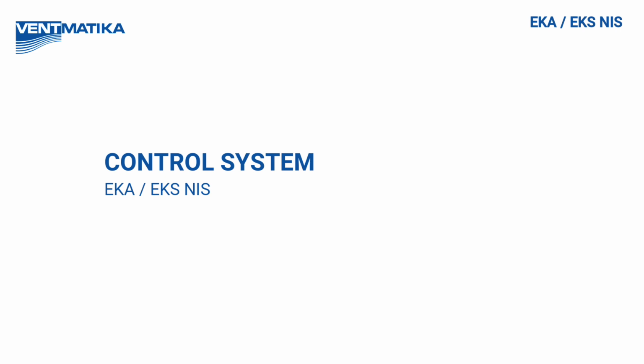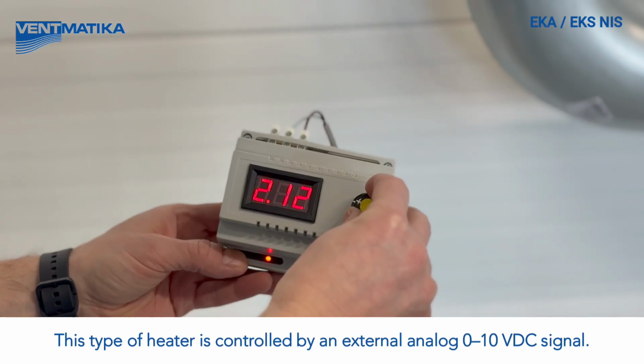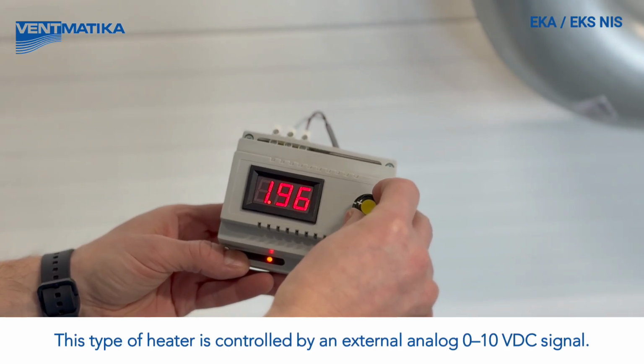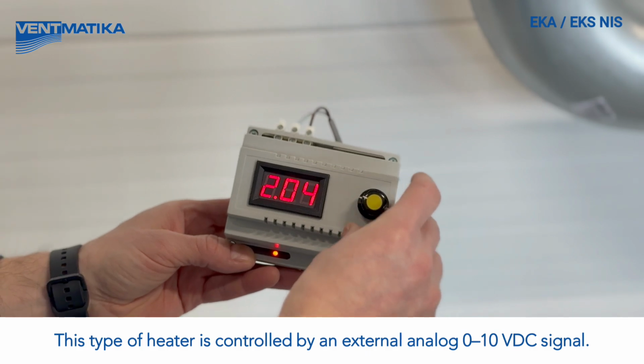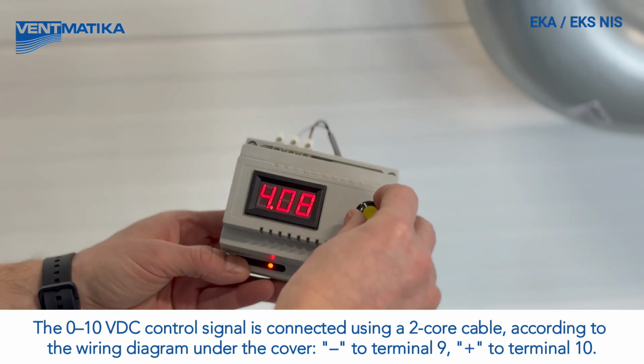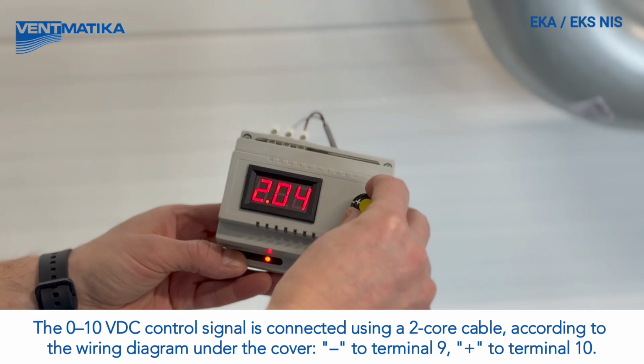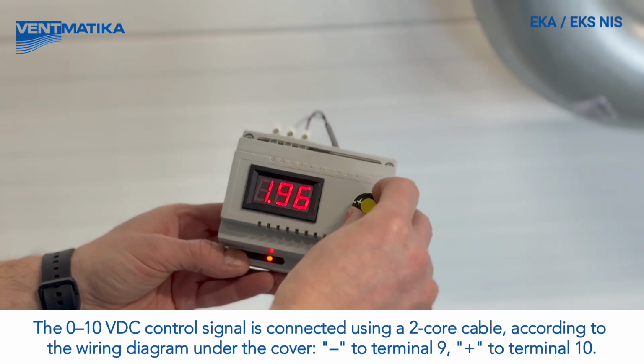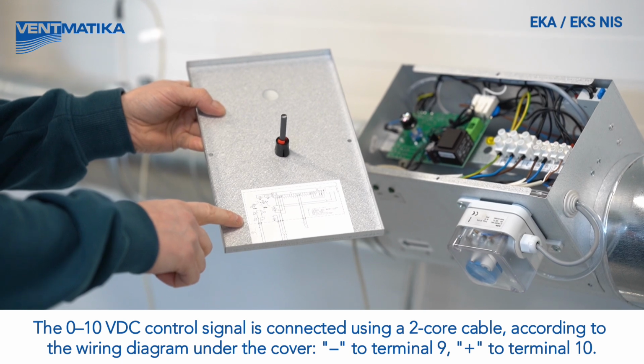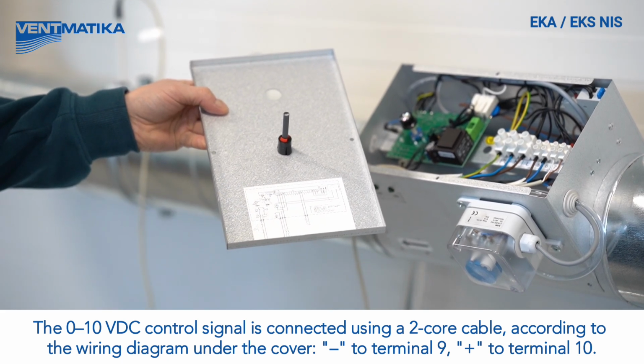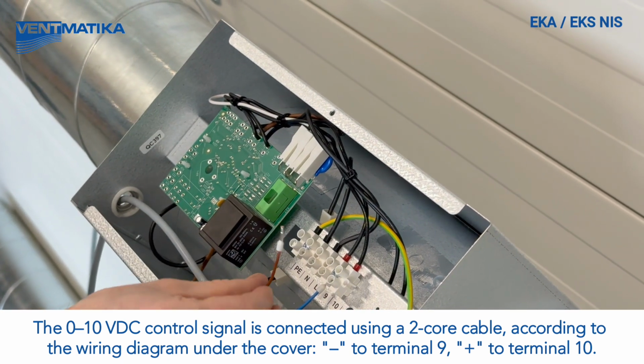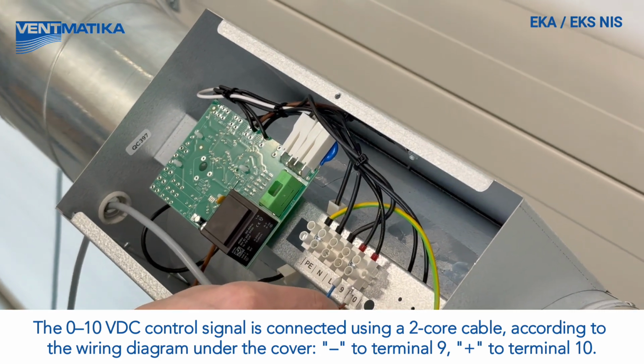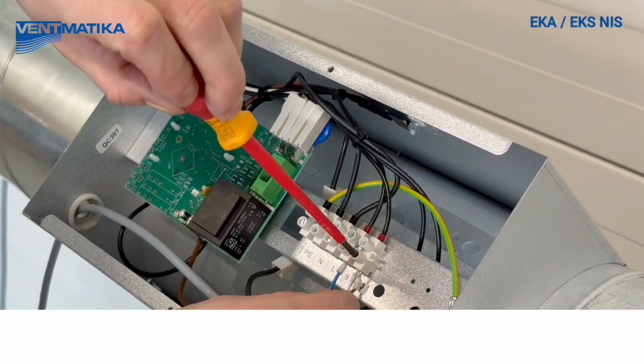Control system. This type of heater is controlled by an external analog 0 to 10 volts DC signal. Electrical connection. The 0 to 10 volts DC control signal is connected using a 2-core cable according to the wiring diagram under the cover. Minus connected to terminal 9, plus connected to terminal 10.